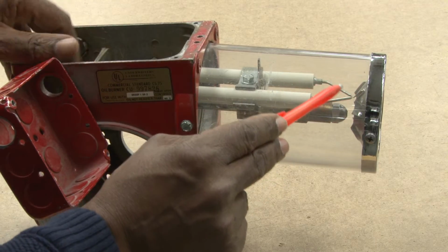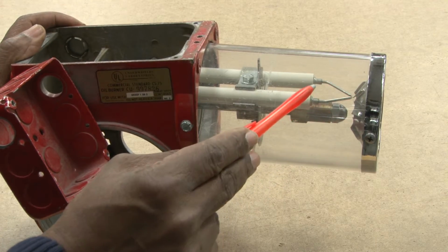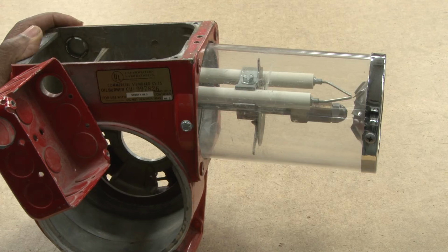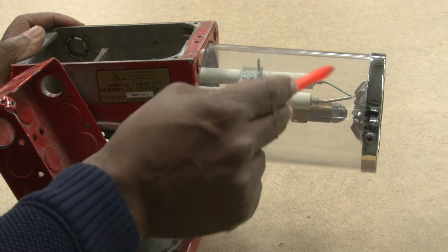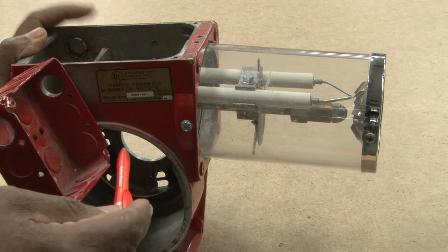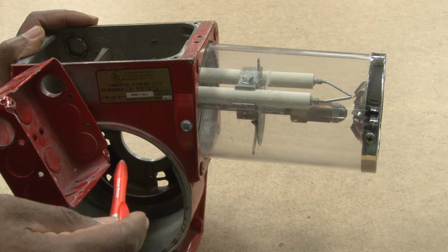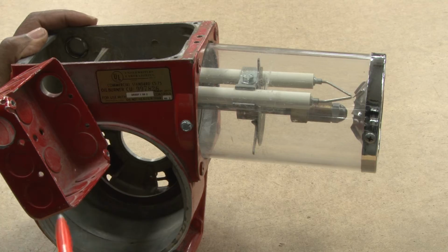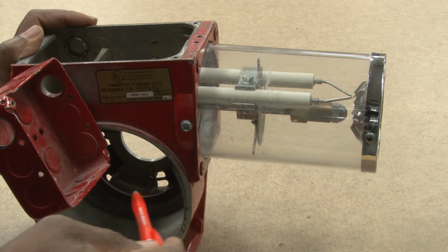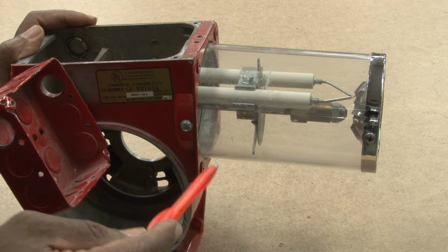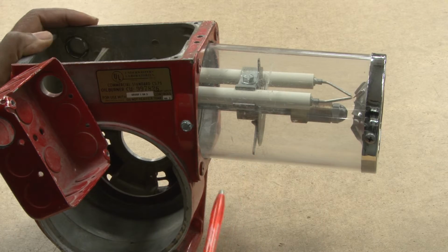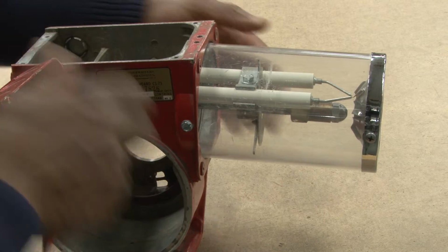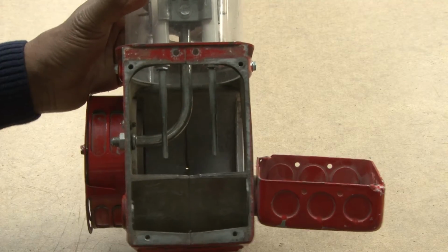So one critical thing is that the electrodes have to be in a proper position to be able to ignite the oil. If the electrode's too high, it will not light the oil, or if it's too close, it can keep it from sparking because it's in the oil path. So the proper position is critical. Even the spacing between the electrodes is very important. We'll see if you can see that.